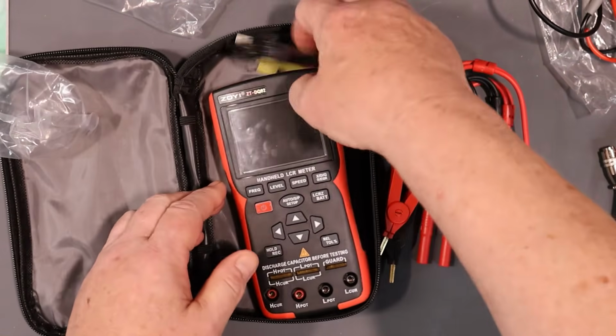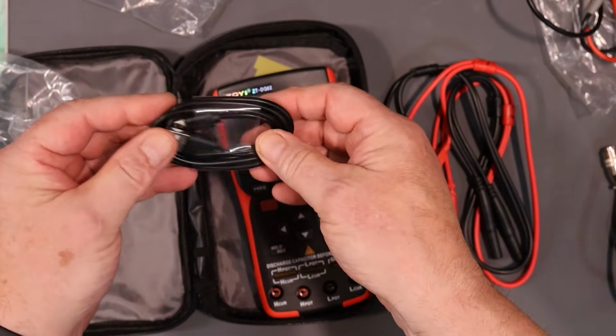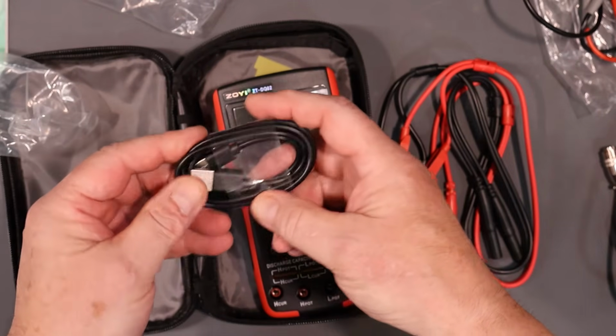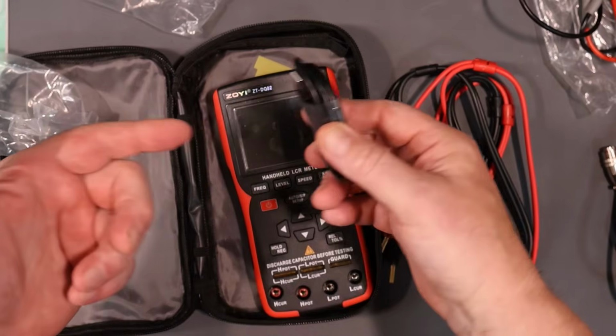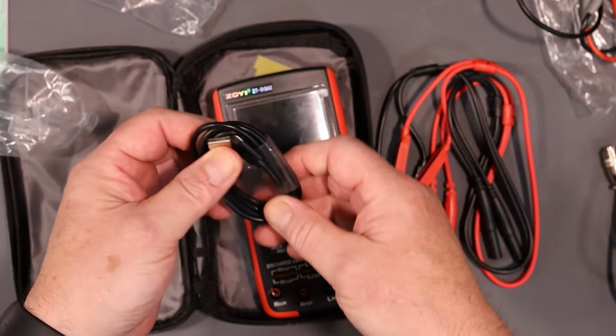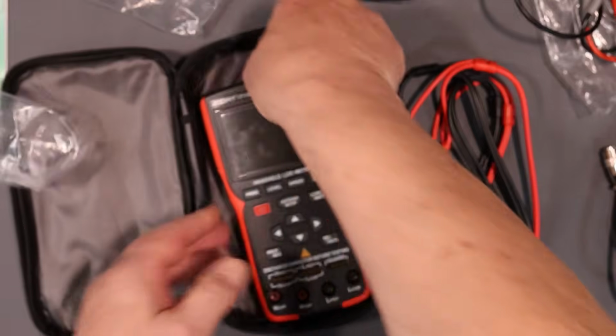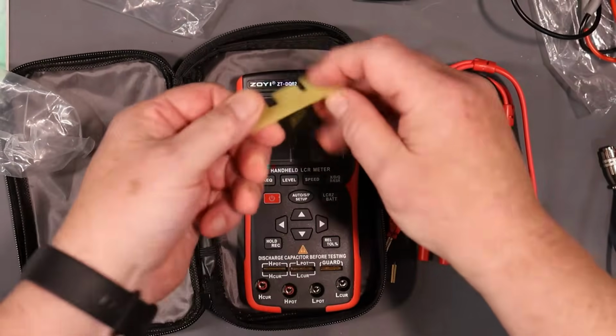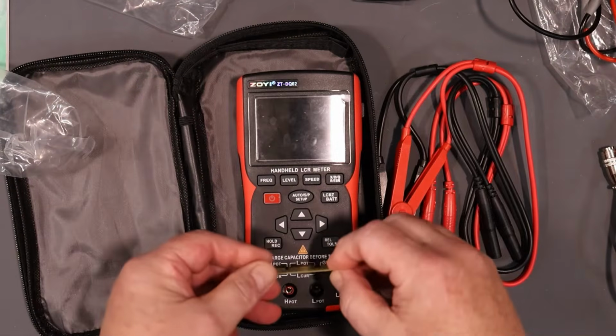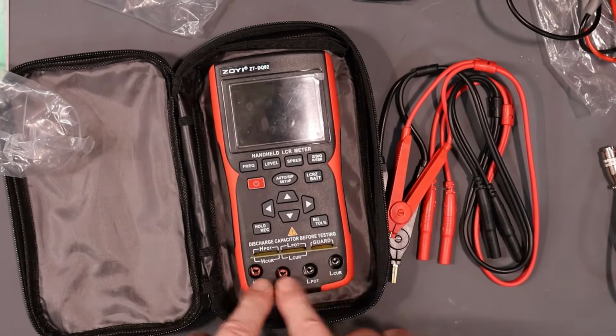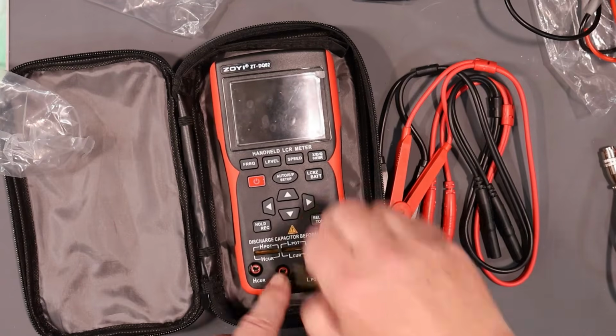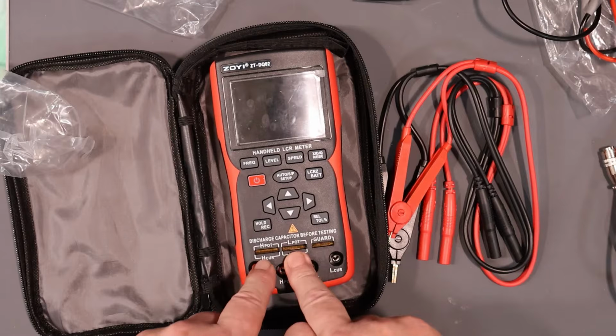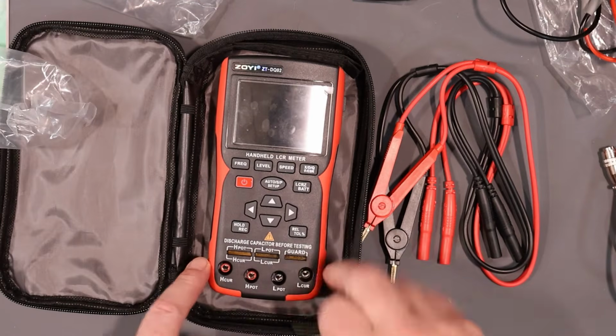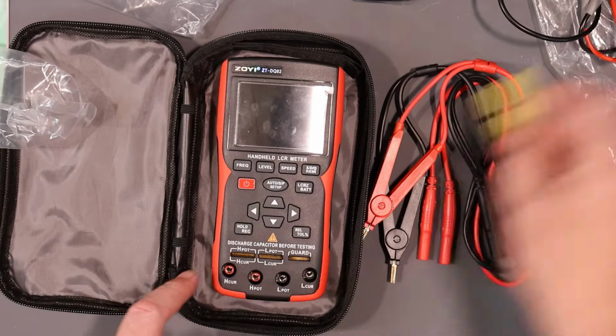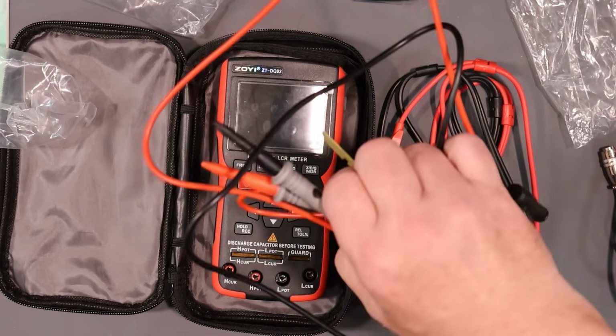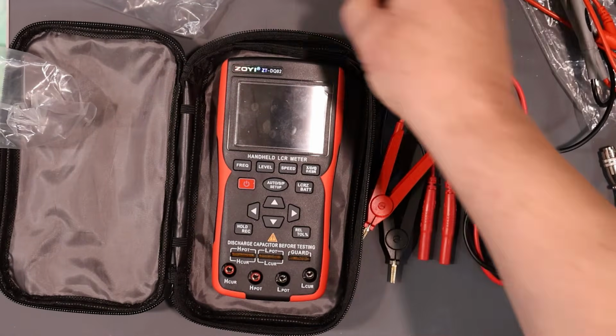And we've also got a USB cable. I would imagine that this is going to be useful for charging it, for getting files on and off, and for doing firmware upgrades. And there is this little insulator here, which just plugs in here for doing 4-wire testing, because normally these blades here all touch for insertion of components. So for doing the 4-wire testing, you want to put these in. Or if you want to go do 2-wire testing, if you really want to, you just leave that out.